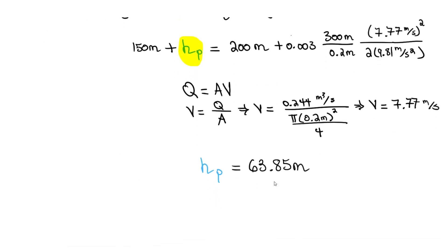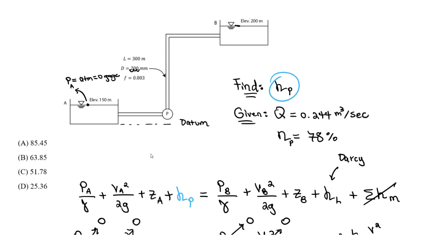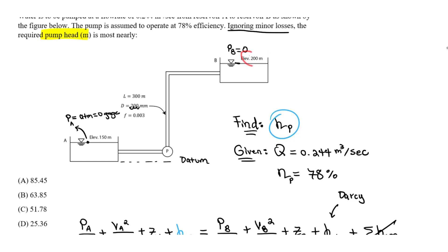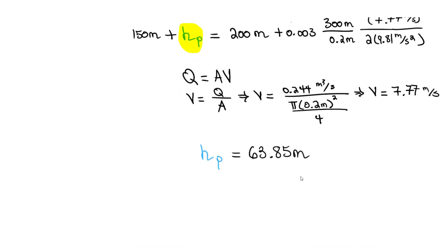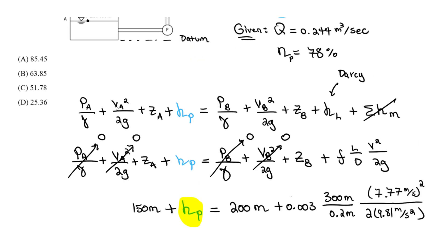The required pump head is 63.85 meters. Note that the elevation difference is only 200 − 150 = 50 m, so why do we need more than 50 m? Because of friction losses due to flow, which depend on the pipe length and diameter. That's why the pump head is greater than 50 m — approximately 63.85 m — and the answer is choice B.